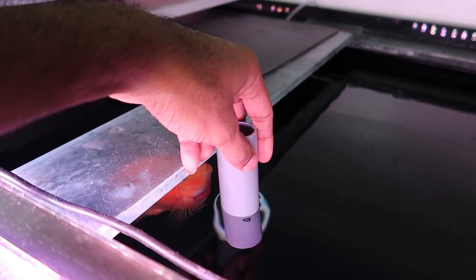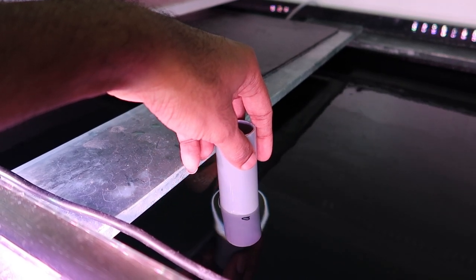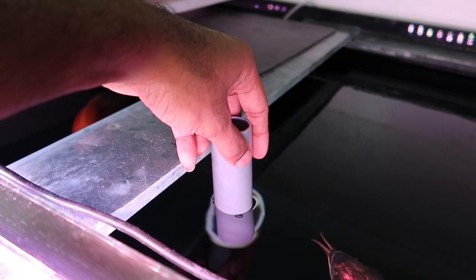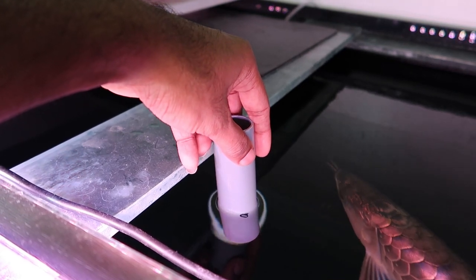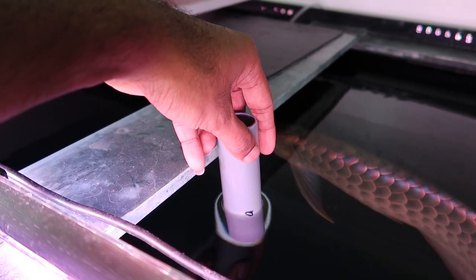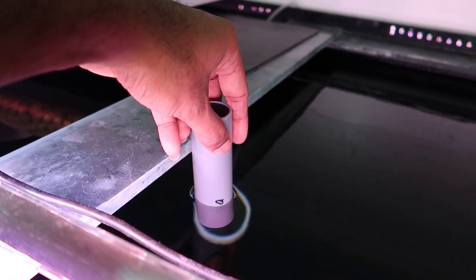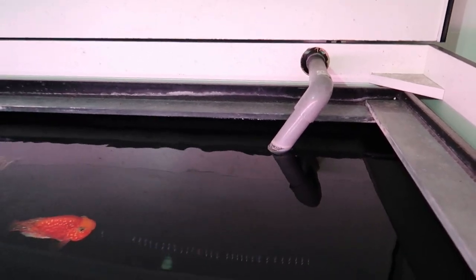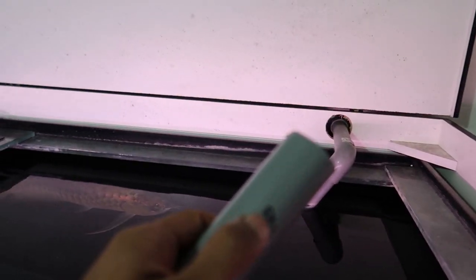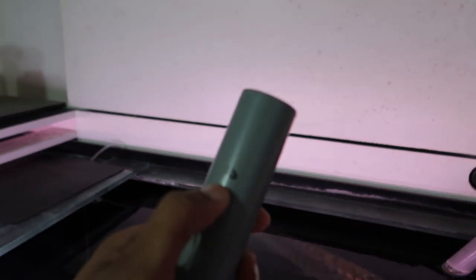Once you turn off your pump, when you turn off your pump it will suck the pipe until this hole, and when that happens your siphon will break. This is how you break your siphon. Number one is your return piping design—you need to use or add a siphon breaker. This is a siphon breaker: a hole.